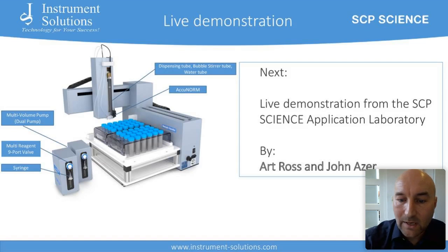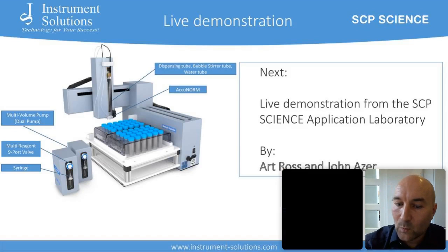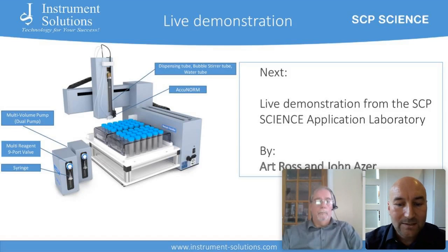So before we move to the live demo, I would like to highlight some of the features of the EasyPREP sample handler. Of course, there is the dispensing tube with a bubble stirrer very close by, also the water tube. Next to that, it's the AccuNORM, which is an ultrasonic level sensor. So it can detect the exact same level to fill up the volume very precisely. You always need one syringe pump, but there's also an option for a second syringe pump. These can have different sizes and volumes of syringes. There's an HF syringe available, and both these pumps have a 9-port valve. So this concludes my presentation, and I would like now to give the word to Art Ross from SCP Science in Canada.